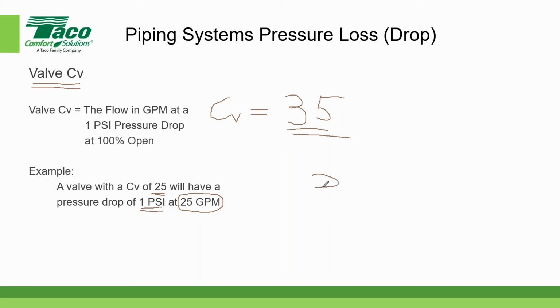That means that valve will allow 35 gallons per minute, GPM, at 1 PSI. So what's cool about the valve CV is that whenever you see the CV for a valve, you know exactly what the pressure drop is at that given flow. In our case, I just arbitrarily picked 35. That means at 35 gallons per minute, the pressure drop is 1 PSI. If the CV was 40, then the pressure drop would still be 1 PSI, but now it would be at 40 gallons per minute. So that's where you can get the pressure drop.